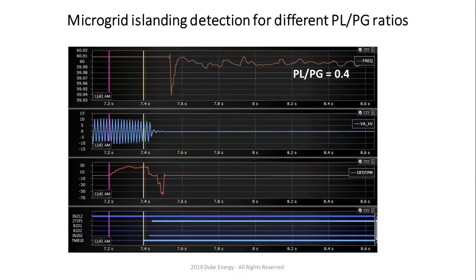What you can see over there is that the yellow line shows when TMB1B. TMB1B essentially in this case is the mirror bit from the battery, and you can see for this particular case, for different ratios for PL over PG and different type of load within the microgrid, this remote bit TMB1B essentially means that the battery inverter has detected the islanding, right? But you can see how the rate of change of frequency has changed during that time much faster, right? And that's DF/DT. You can see on the left side that range. And I can tell you that we have tested different ranges. I have pictures over there so you can see pretty much where the set points are.